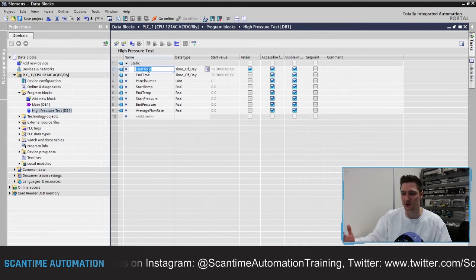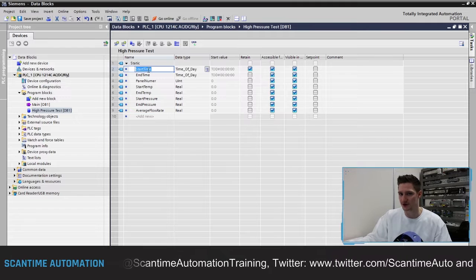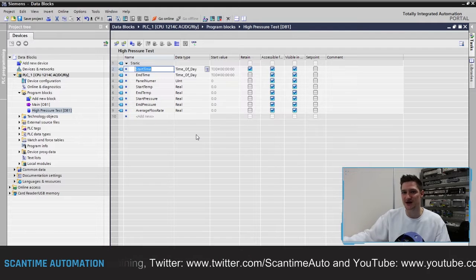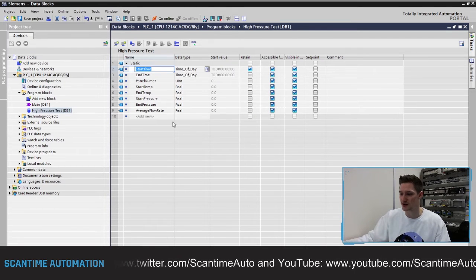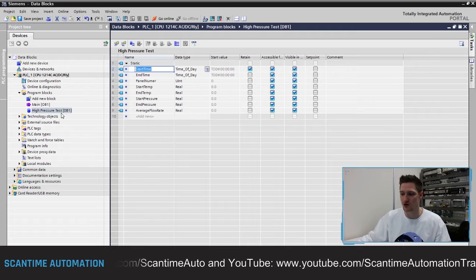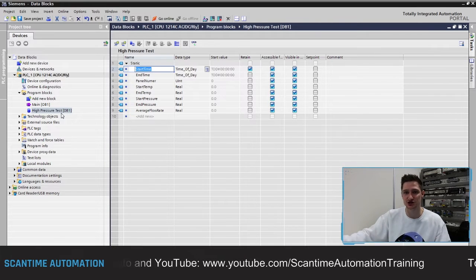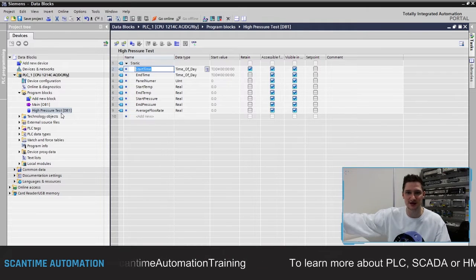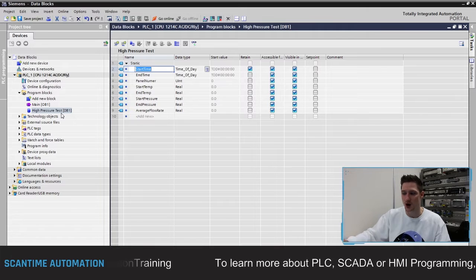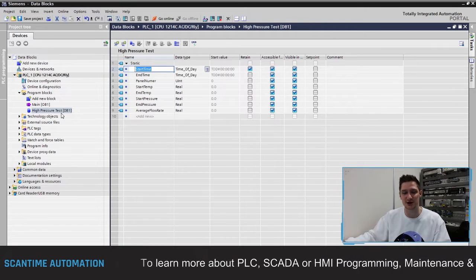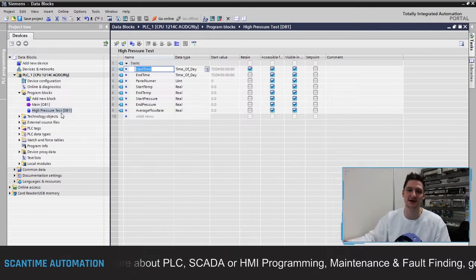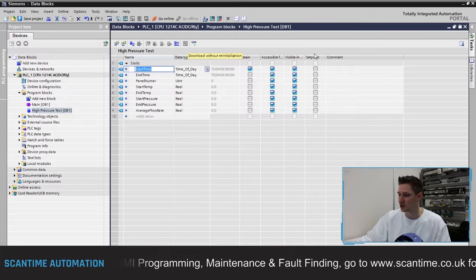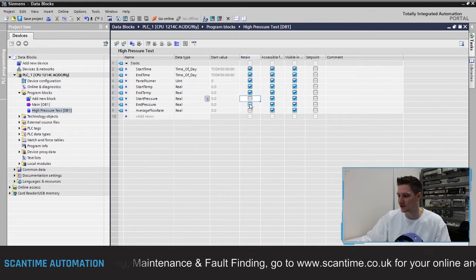A great feature of TIA Portal is that when you create a data block, it becomes optimized — unlike in Step 7. What we mean by optimized is that we don't need to look at its addressing; it's all symbolic. So when I want to access this inside of the program, I would simply type 'High Pressure Test.start_time' and the PLC does all the addressing work. We can make it unoptimized and set the addressing ourselves, but we'll leave it optimized so we don't have to worry about data block addressing.